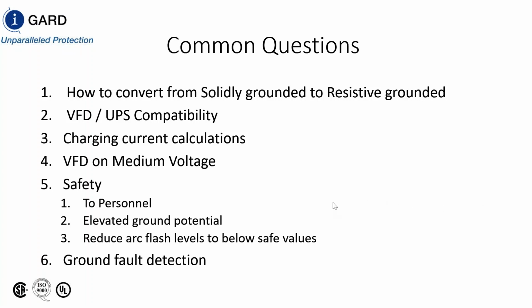Thanks, Sergio. Another question, is there an industry standard for stating breaker tripping priorities? For example, always trip, never trip, etc. Always trip, never trip, for priorities? Yeah, so is there an industry standard for how you should be setting your breaker tripping priorities? If you were going to employ our DSP system where it has second fault priority trip, it's not the breaker that makes the determination, it's the load that's connected to that breaker that makes the determination.